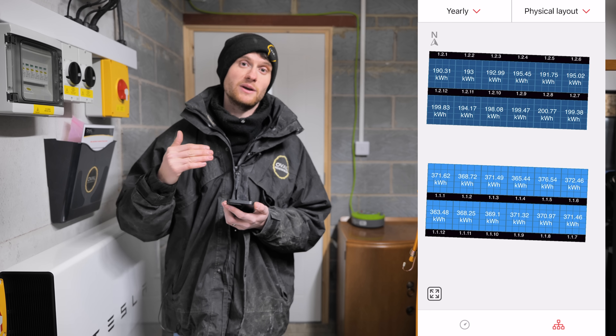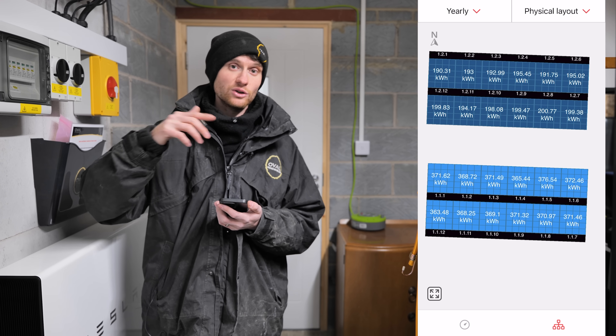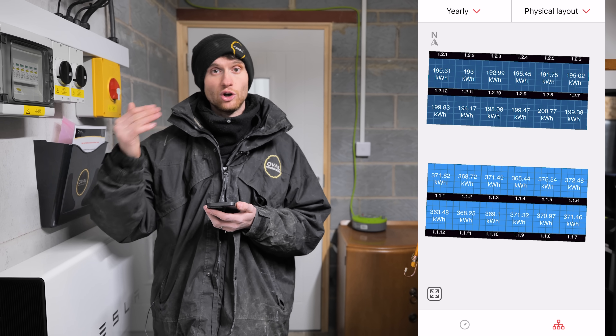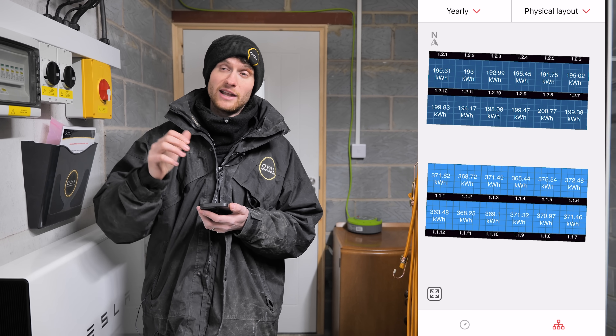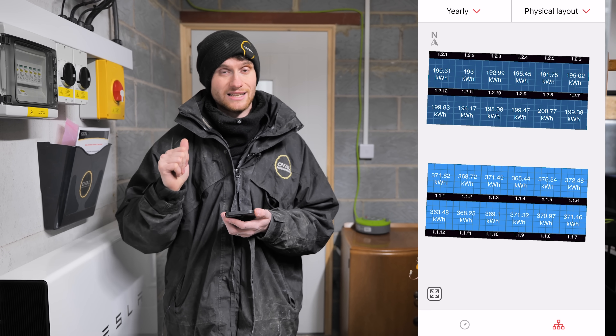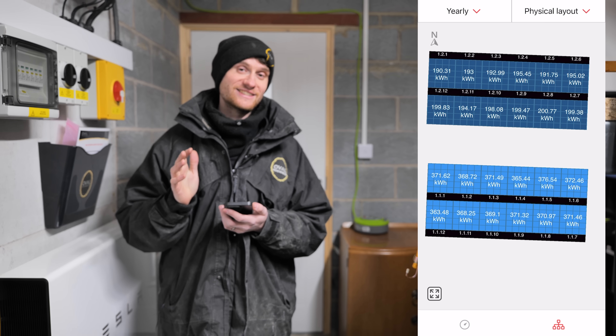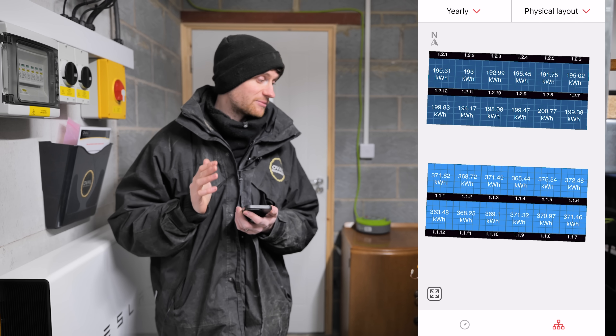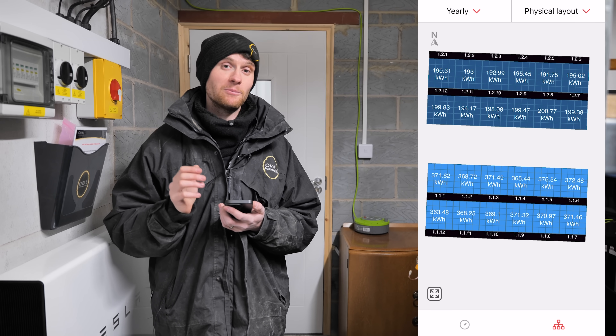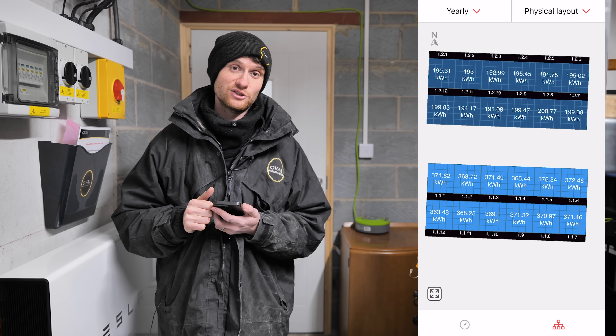This roof was gifted with equal space on the south and north-facing sides. But if there were lots of vents, Velux windows, or dormer windows on the south-facing roof and a large amount of north-facing space, this site makes a strong argument to utilise that north-facing roof. Hopefully you agree — 35% of total generation came from the north, and those north-facing panels produced about 54% of what the south-facing ones did. That's unbelievable numbers.